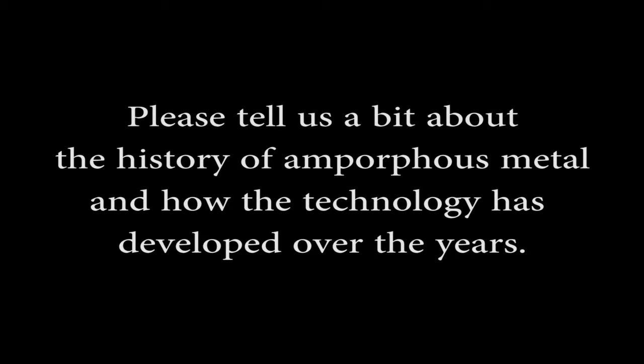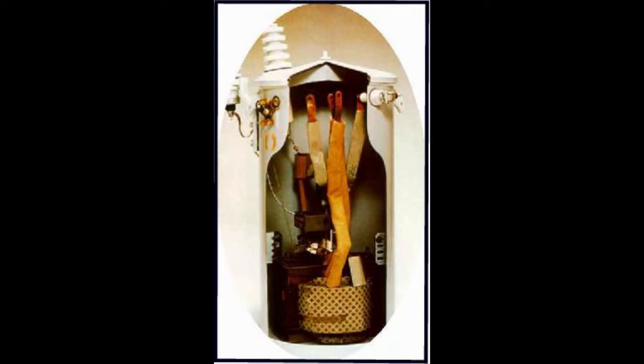The next big development was in the mid-1980s when the U.S. government, through their Electric Power Research Institute, or EPRI, saw the energy savings potential for this iron-based amorphous metal for electricity distribution, where the distribution transformer, the last transformer in the distribution grid, hanging on the poles or on a pad in front of your house, distributes the electricity to the end user. EPRI provided funding to Allied Signal, and we were working with GE at the time, and we made 1,000 amorphous metal distribution transformers and put them all over the country.